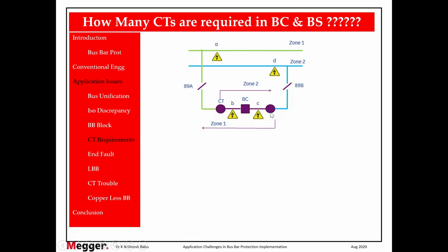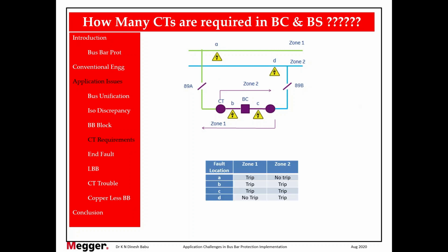CT here, CT here. We are going to analyze this case with 4 conditions: fault in location A, fault in location B, fault in location C, fault in location D. Let us see what will happen. This chart will occur. Now let us see, forget about B, C, D. Let fault be in A. Okay, fault in green color area. Bus 1 will trip. All the bays connected to zone 1 and bus coupler will trip. Perfect. So zone 1 trip, zone 2 no trip. Second, fault in location B. This is the overlap region shown in purple color. That means what will happen? Both zones will trip. Zone 1 will trip, zone 2 will trip.